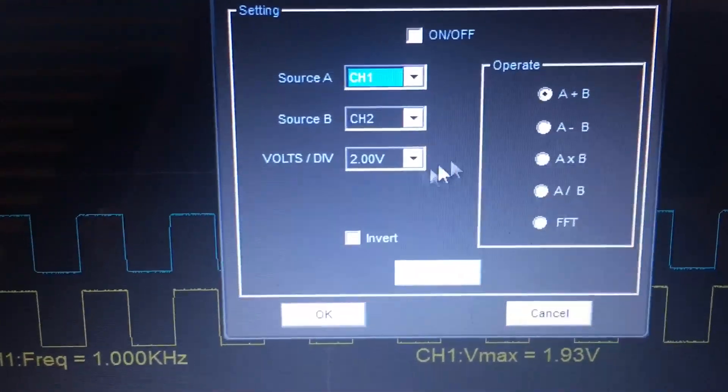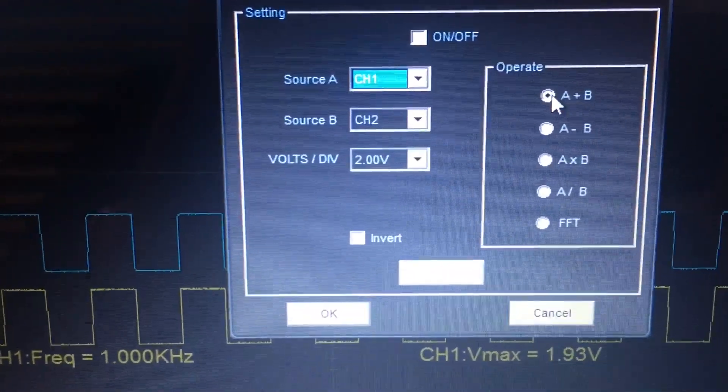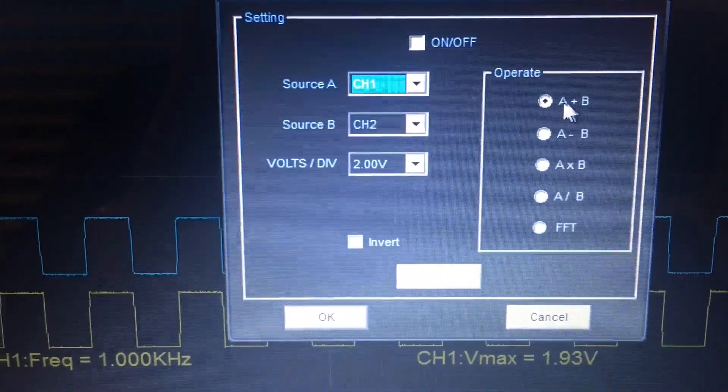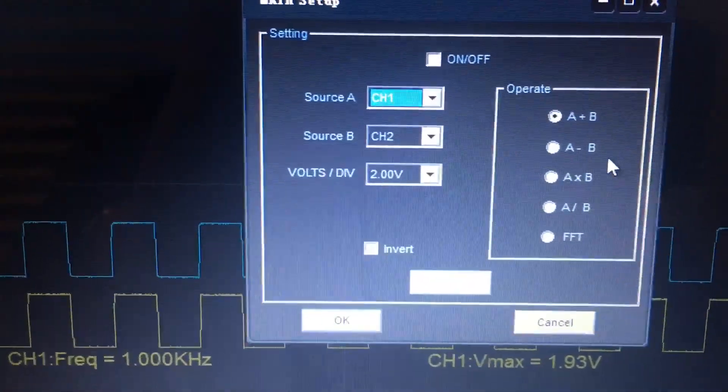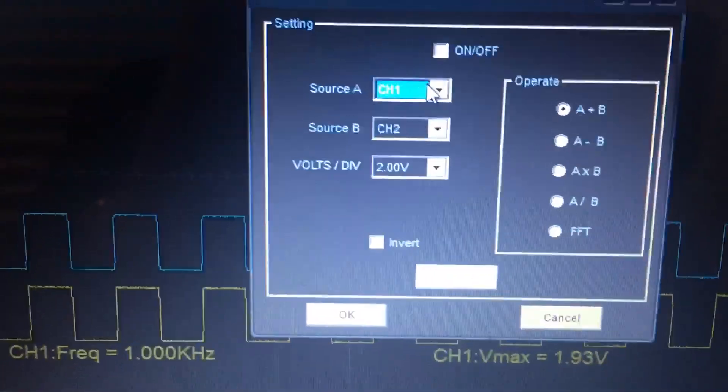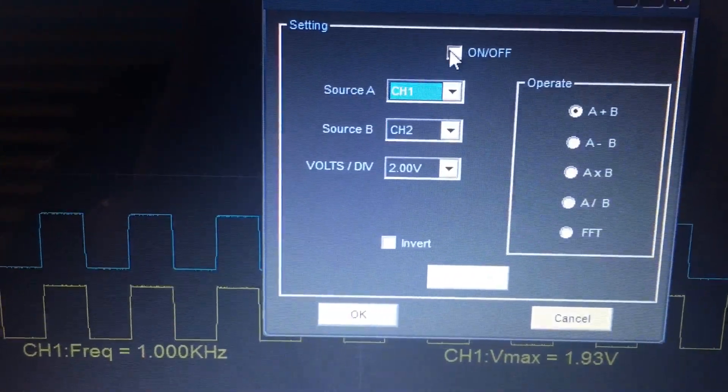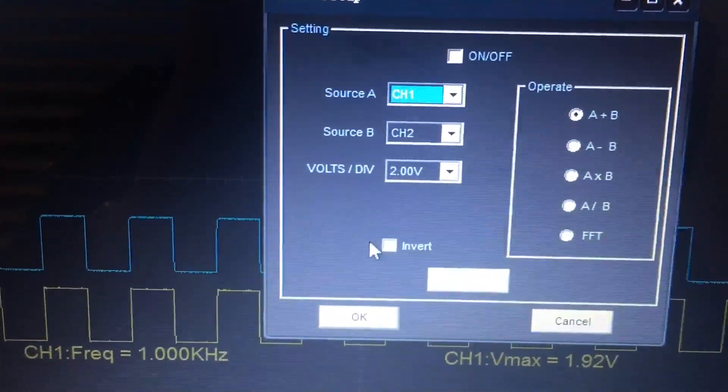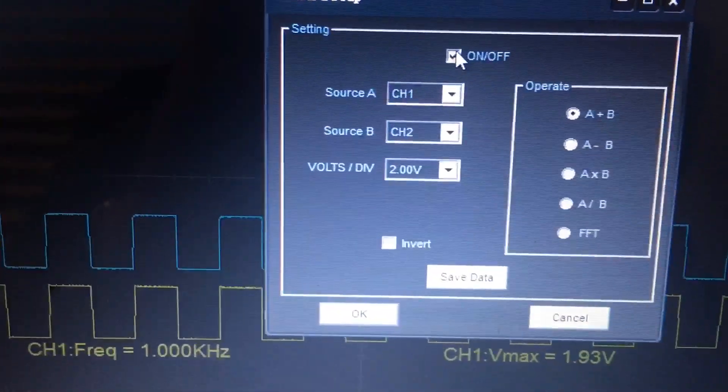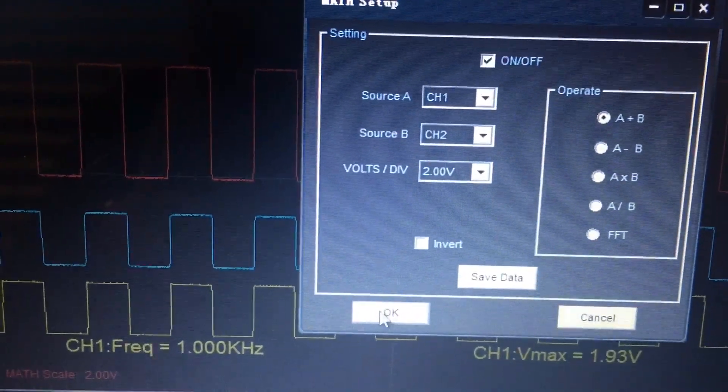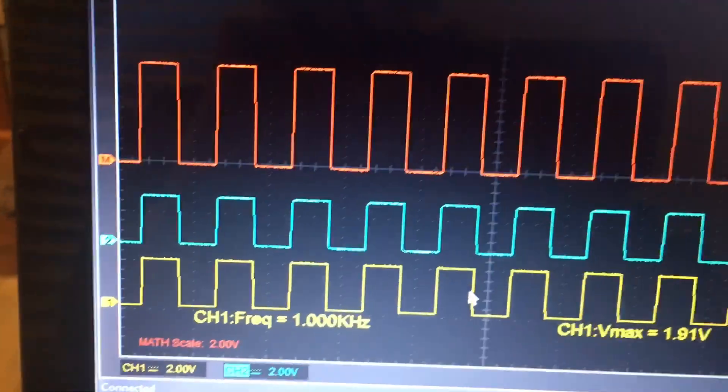Let's start with the basics, so let's just do some simple addition of A and B, channel 1 and 2 if you prefer. Select display and make sure the invert is not on, otherwise it might mess you up. And what we see here on the screen in the red channel with the marker M...